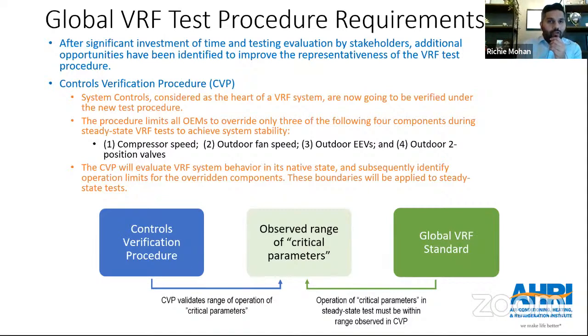Before a steady state test, so during a steady state test for VRF equipment, we try to lock down the compressor speed, we try to lock on the expansion valve settings, we try to lock on the outdoor fan speed. And we do all of these three things and beyond for a reason, so that we can get a repeatable test result, a reproducible test result, and a representative test result. But how are we sure that the settings for compressor speed, the fan speed, the expansion valves which are being used are really what you would end up seeing in the field, or are they something which is an anomaly, just so that you can get the best ratings out there in the lab, right?